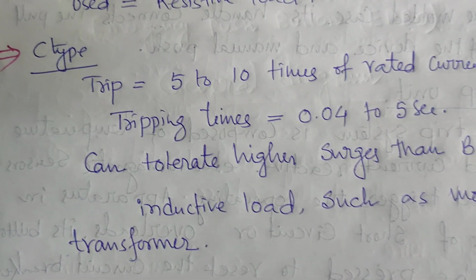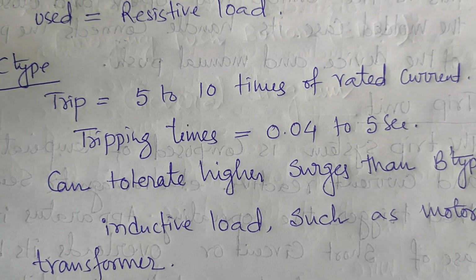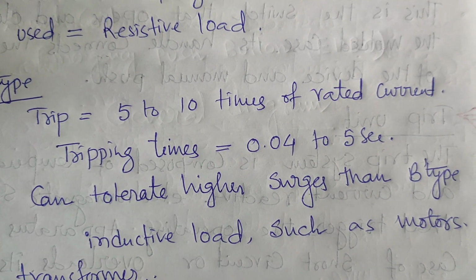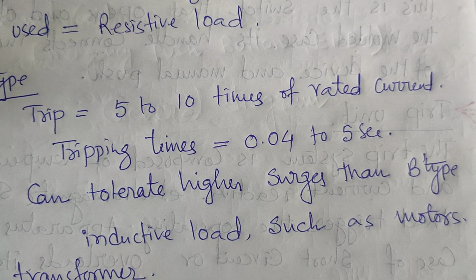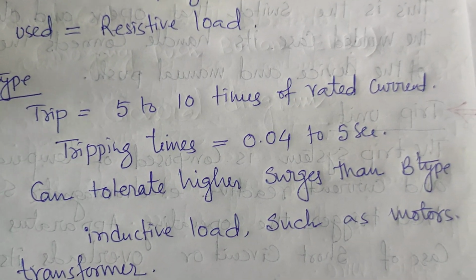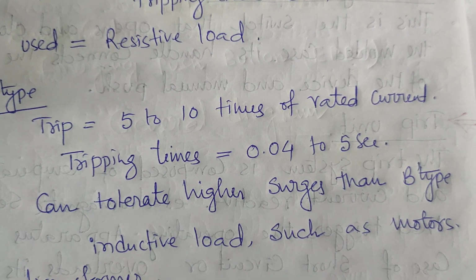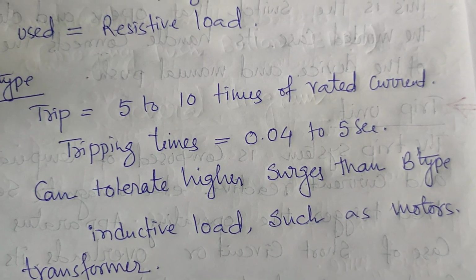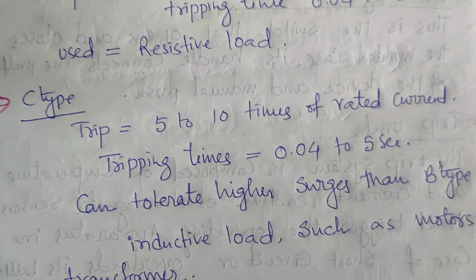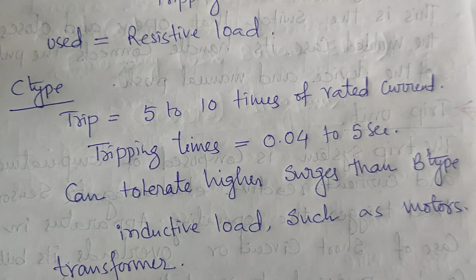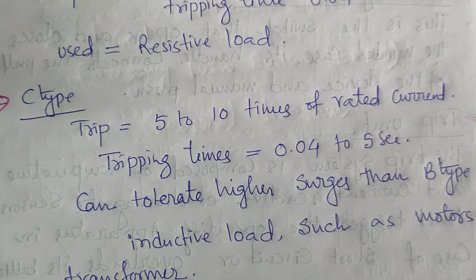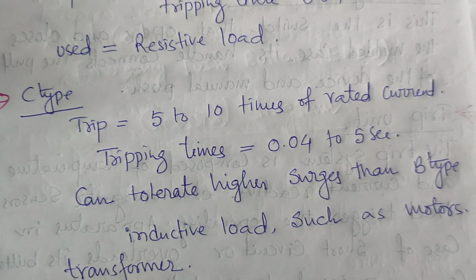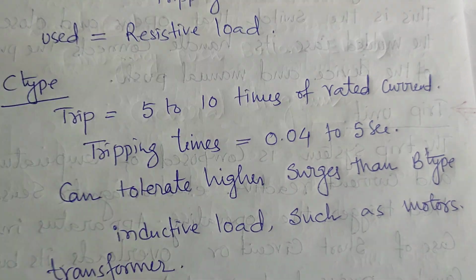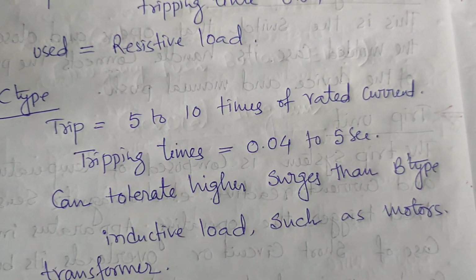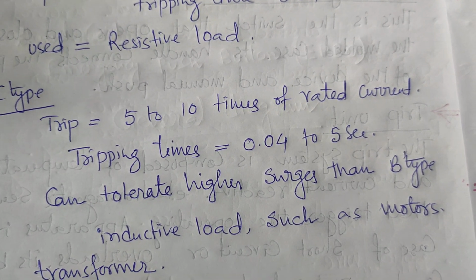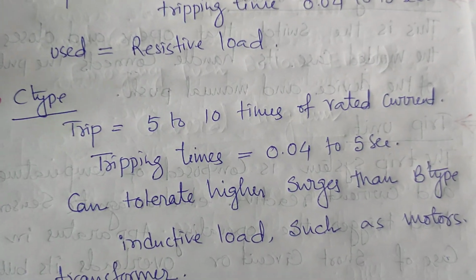And the C type MCCB: if 5 to 10 times the rated current flows there, the tripping time will be 0.04 to 5 seconds. It can tolerate higher surges than the B type. The B type cannot sustain a high surge, but the C type can, because if a system is connected with the grid, with lots of systems and networks, a huge number of big and small faults can occur. So if there are small and big faults, there will be surges and voltage peaks. If this surge will be there, the C type MCCB should be used.